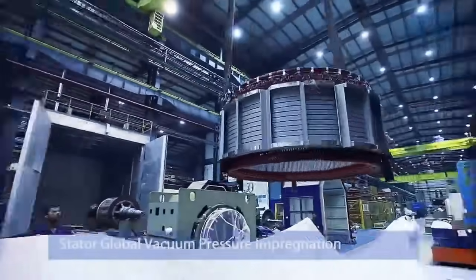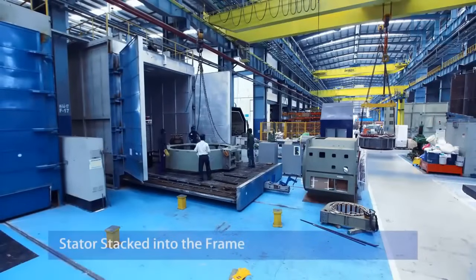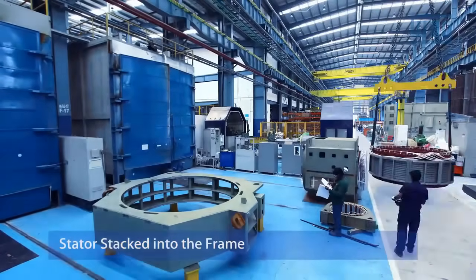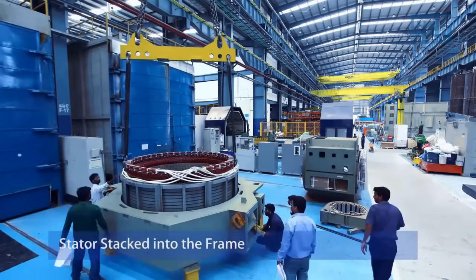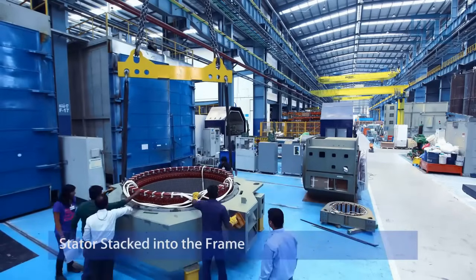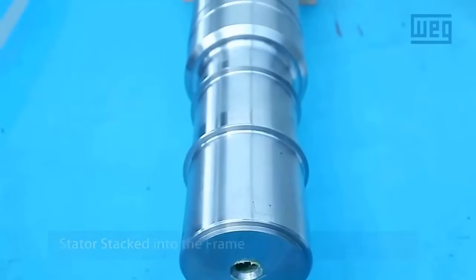Stator Global Vacuum Pressure Impregnation enhances the stator's insulation properties and overall reliability. The stator windings are impregnated with epoxy resin under vacuum and pressure. This process eliminates air gaps, enhances thermal conductivity, and protects against environmental factors like moisture and contaminants.